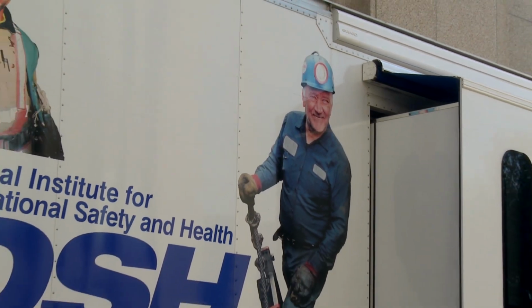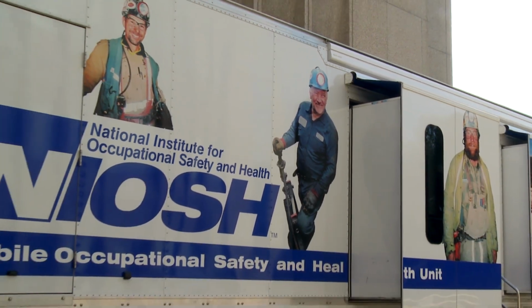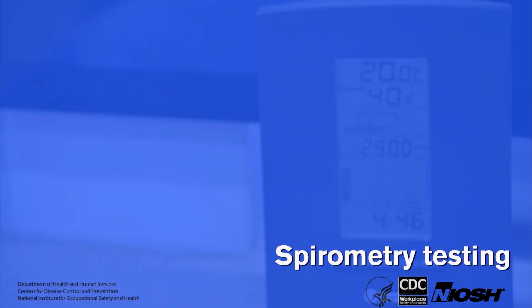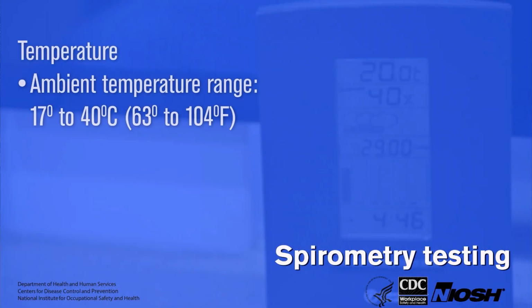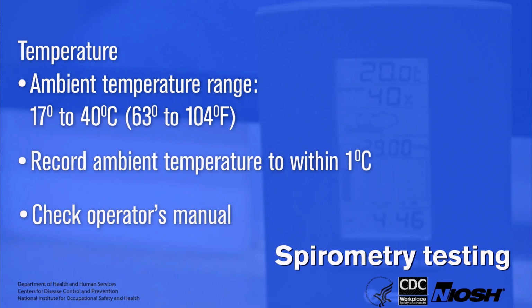Before we discuss spirometry testing equipment, we need to review some environmental considerations for the testing area. The American Thoracic Society recommends that spirometry be performed at ambient temperatures between 17 and 40 degrees Celsius. That's between 63 and 104 degrees Fahrenheit. Testing performed outside of these ranges may cause inaccurate reporting of the worker's results.